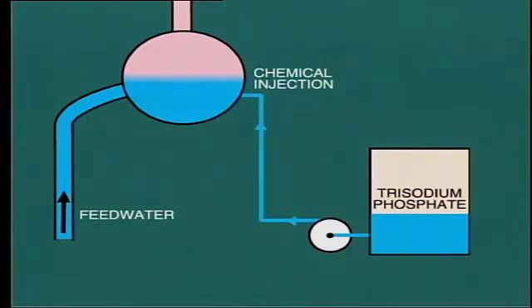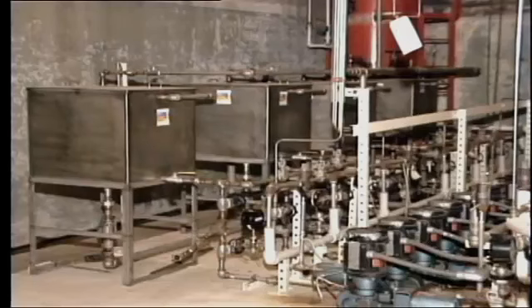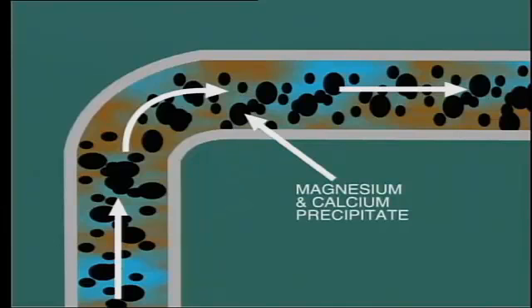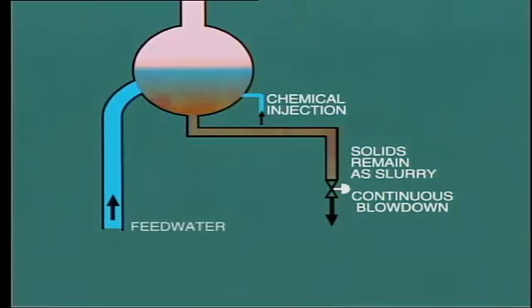We'll be talking more about corrosion later in this module. Even with all these precautions and controls, there is still a tendency for the concentration of solids to build up in the boiler water. For this reason, an attempt is made to prevent scale formation by injecting a chemical dispersant such as phosphate into the boiler water, usually added at the boiler drum via a high pressure pump. Phosphate has the effect of keeping the magnesium and calcium precipitate in suspension by dispersing the solid particles throughout the water. The result is that instead of forming a hard scale, the solids remain as a slurry to be discharged from the boiler through the continuous blowdown line.